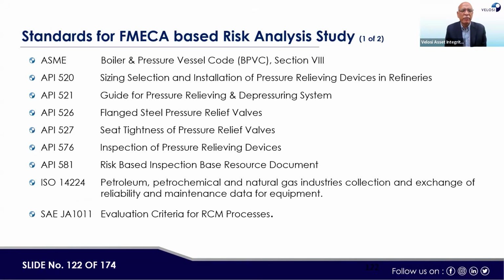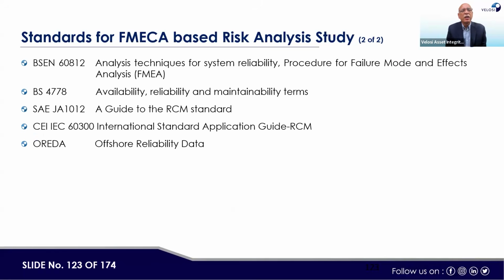So these are the standards that were applicable in the project: ASME, mainly ASME 8, then API 520, API 521, 526 and 527, API 576, 581, and ISO 14224, and SAE JA1011 for the RCM or FMECA process. Then BS EN 60812 is the FMEA analysis, and BS 4778 for availability, reliability, and maintainability terms. A guide for the RCM standard was JA1012, the international standard application guidance for RCM, and OREDA for the reliability data.